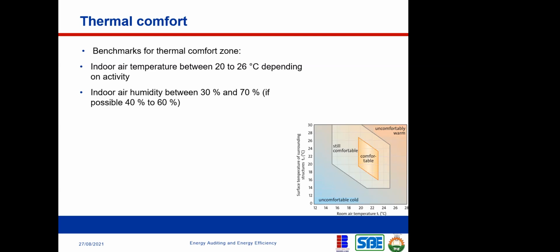That's not all. There's another factor, like I said: indoor humidity between 30 to 70, or maybe between 40 to 60. So as long as your indoor humidity is within this range and your temperature is between 20 to 26, normally most humans should be comfortable. So there's no point running your air conditioning system at 17 or 16 degrees centigrade. I keep emphasizing this point because it's a means through which a lot of energy is being wasted by the air conditioning system.